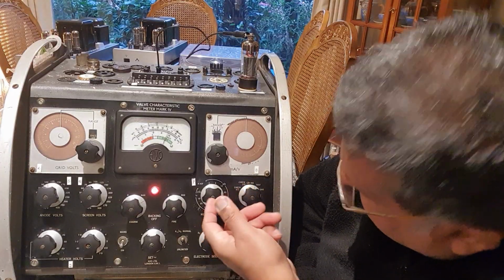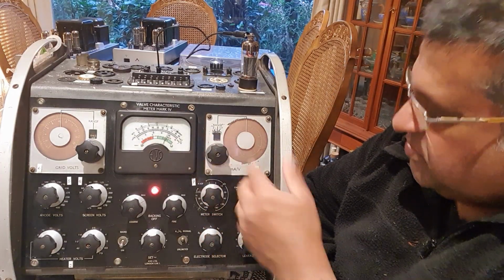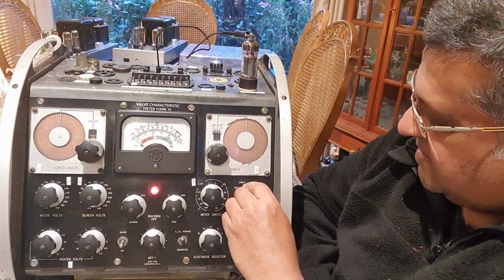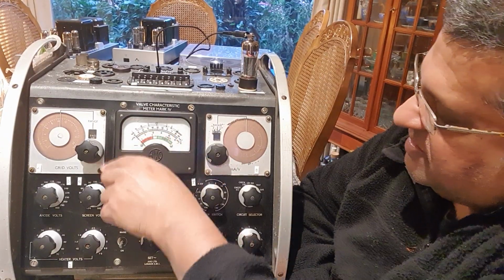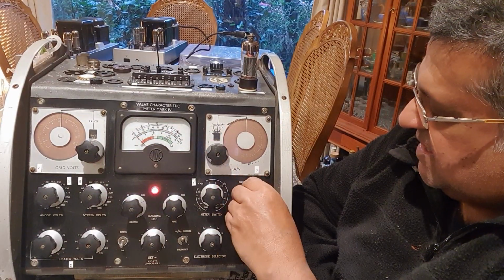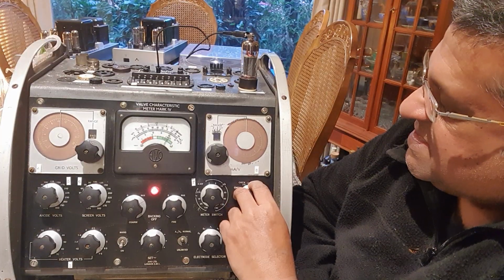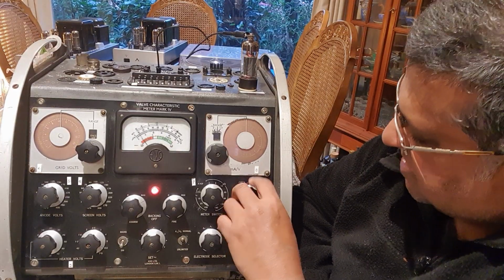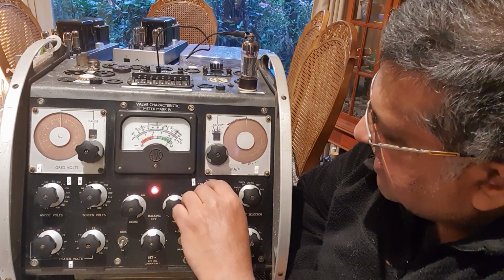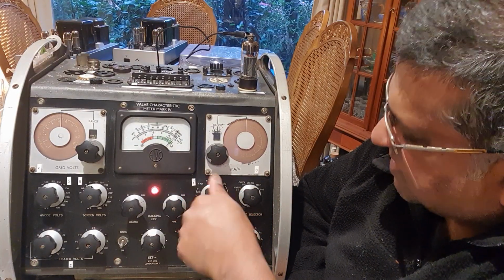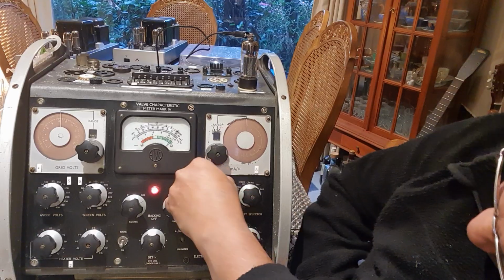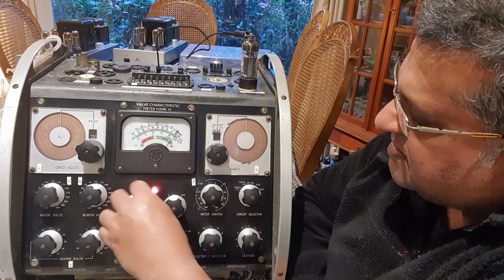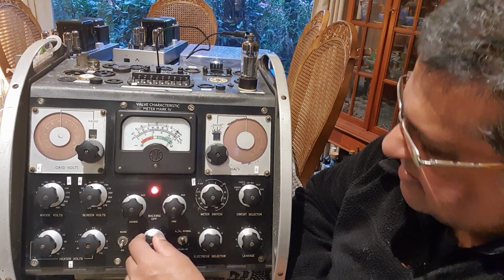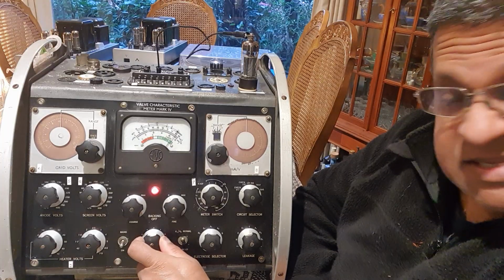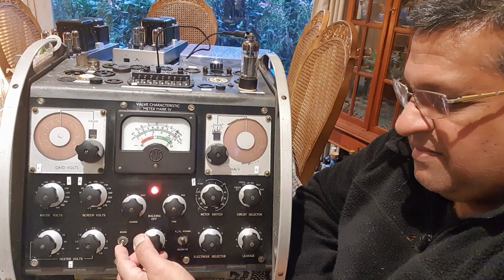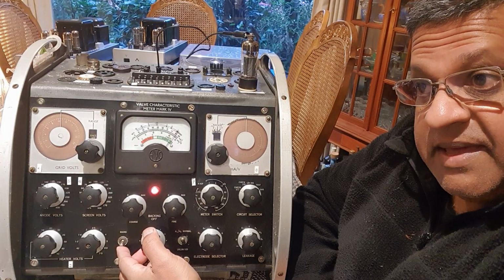And the final test would be the gas leakage test. By now, if there's a leakage, we would have known. But anyway, the leakage test shows that it goes back to 0. There is no gas leakage. So the test is pretty much complete. We can shut down by putting all these to 0, and then we can put these 1 to 100 as well before we do the backing off. Yeah, that's it. Test is complete, and that's how you check a valve, especially one with a top cap, and it's an EL360.